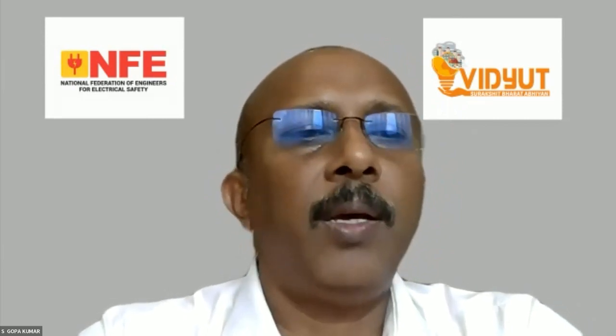The earth conductor of TNS should be insulated. Question from Mr. Amritlal. No, it can be, the functional earthing must be insulated. So your question, earth conductor. Please note that earth conductor or earthing conductor means the conductor from the earth bus bar to the earth electrode or some kind of buried metal part. That conductor must not be insulated. Otherwise, a protective conductor can be insulated. It depends on the situation. Functional earthing must be insulated. So earthing conductor need not be insulated. It has to be a bare conductor.